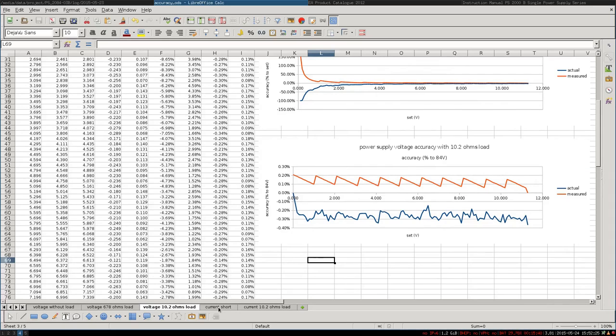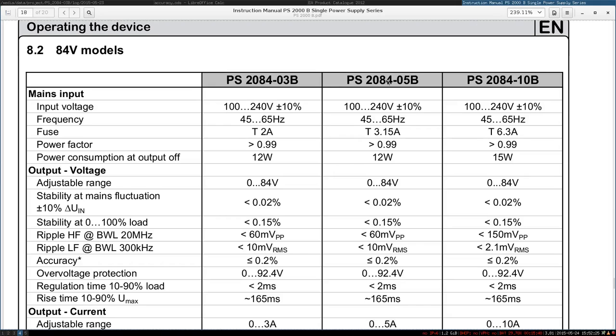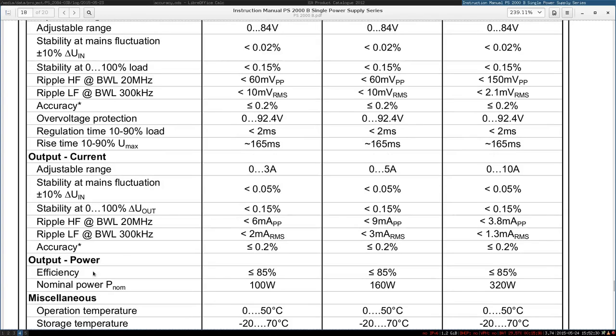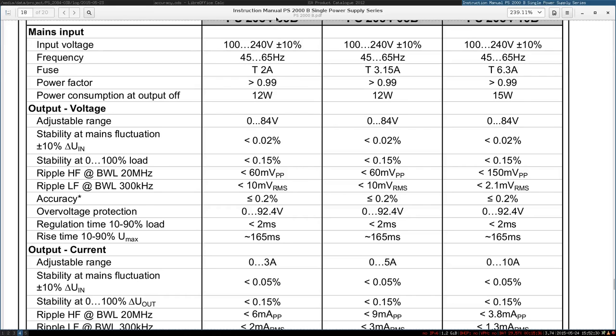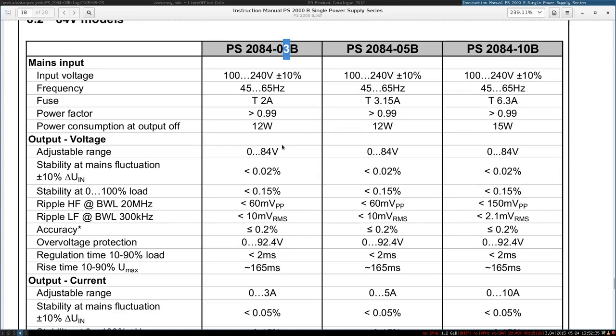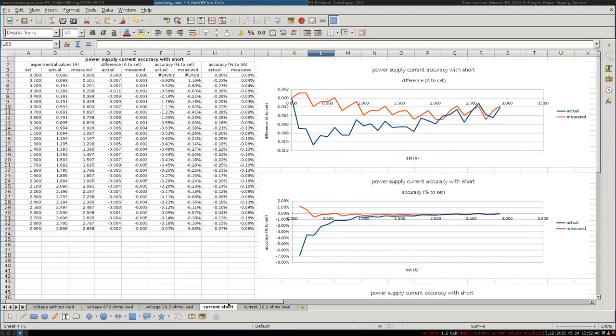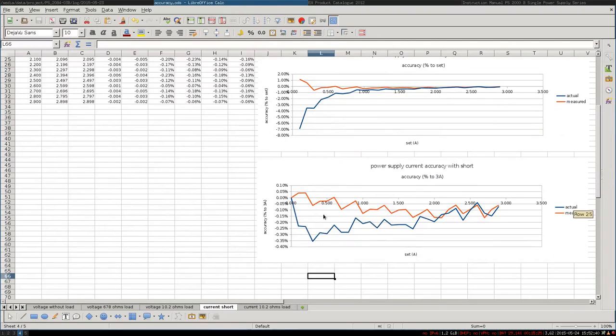Now, if you look at the current, it's the same thing. The accuracy is minus 0.2% of the nominal, and the nominal for us is 3 amps. And if we look at the current, again, the accuracy here, we can see that in the beginning it doesn't respect it, but afterwards the difference is not that high, it's just minus 0.40%.